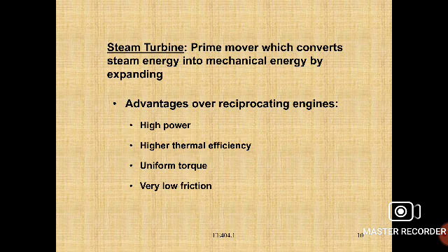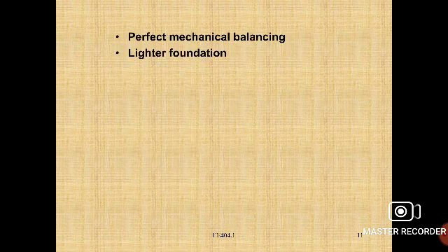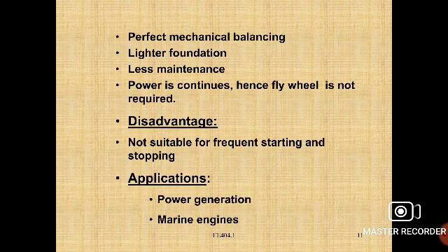It can also be directly coupled to high speed machines. Governing is easy, maintenance is less, and it requires less floor area for a given output. Exhaust steam is free from oil, hence the condensate can be reused as feed water. Next, the disadvantages: steam turbines are not suitable where frequent stopping and starting is necessary. Also, a condenser must be provided to take advantage of the greater range of expansion, right?